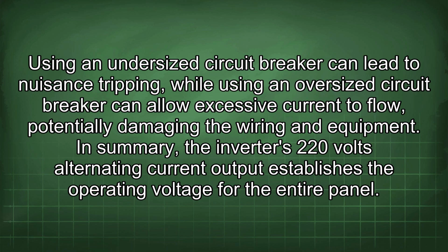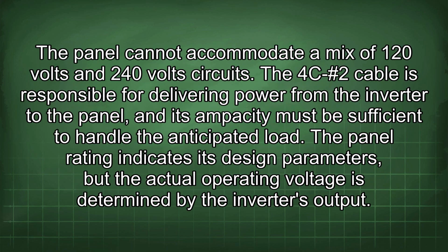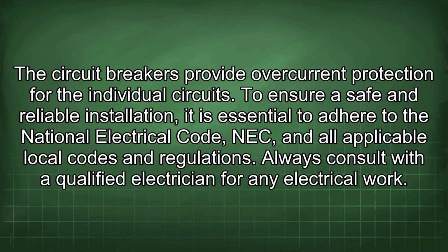In summary, the inverter's 220 volts alternating current output establishes the operating voltage for the entire panel. The panel cannot accommodate a mix of 120 volts and 240 volts circuits. The 4C-#2 cable is responsible for delivering power from the inverter to the panel, and its ampacity must be sufficient to handle the anticipated load. The panel rating indicates its design parameters, but the actual operating voltage is determined by the inverter's output. The circuit breakers provide overcurrent protection for the individual circuits.